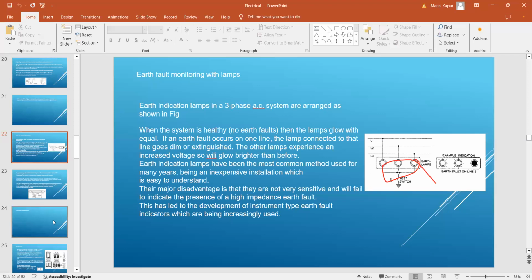If an earth fault occurs on a line, the lamp connected to that line goes dim. So suppose there is an earth fault on line L3, can you see this light getting dim or extinguished? It might be possible the bulb will not light at all. The other lamps experience an increased voltage, so they will glow brighter than before. Earth indication lamps have been the most common method used for many years, being inexpensive and easy to understand. Their major disadvantage is that they are not very sensitive and they will fail to indicate the presence of a high impedance earth fault. This has led to the development of the instrument type earth fault indicator.